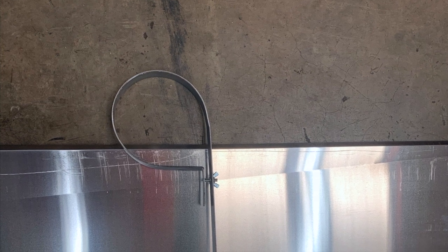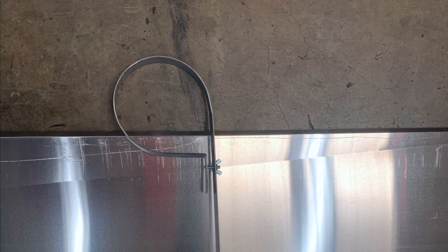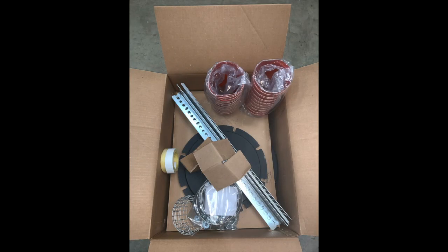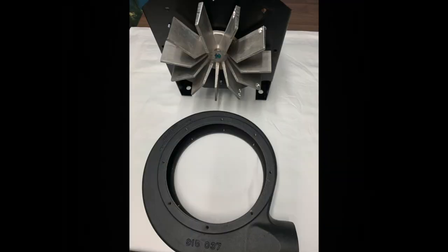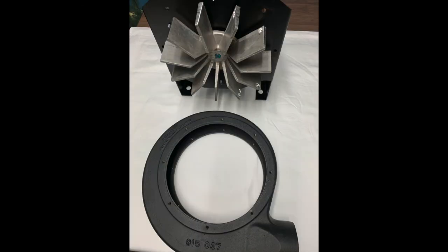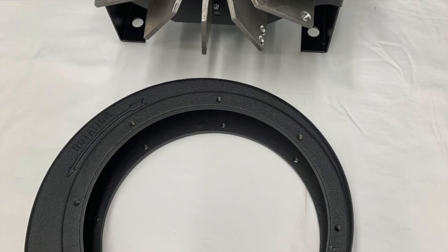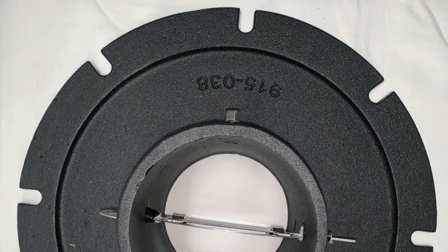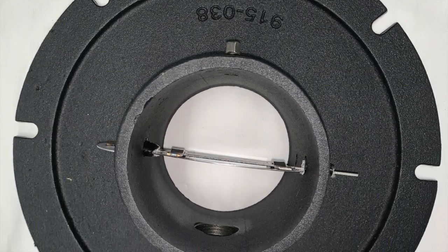Tightening the wing nuts on the side reflector supports, you can tap them with a hammer to square up the reflectors as necessary. The vacuum pump ships partially unassembled. Take great care as the impeller is balanced and fragile. Placing the gasket on the scroll and then placing the motor frame with the impeller down into the scroll and bolting down with approximately 40 foot-pounds of torque.